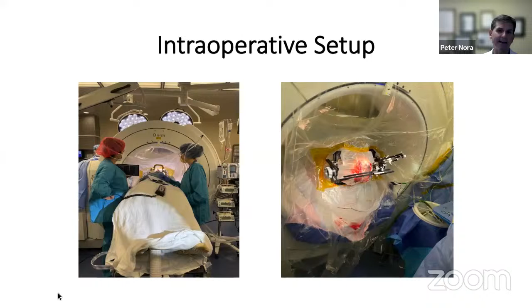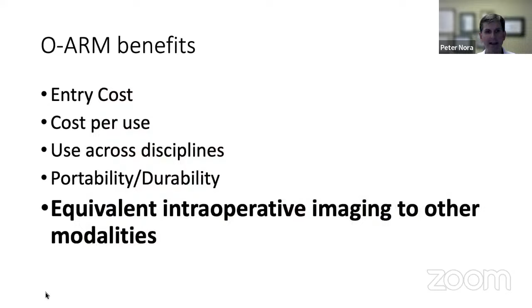And on the right, this is my view. You can see I can work in a sterile field. That's a CRW stereotactic frame. There's a microelectrode driver that's actually attached to it. That's what my workspace is, which is very comfortable. The nice thing is, I also don't really have to change anything to do my O-arm scan. So I can scan with the cannula in the brain, electrodes in the brain. There's nothing that has to be changed or moved. This probably moves towards the feet and towards the head about 8 inches, and that gives me plenty of room to work and get scans on demand as I need, okay?